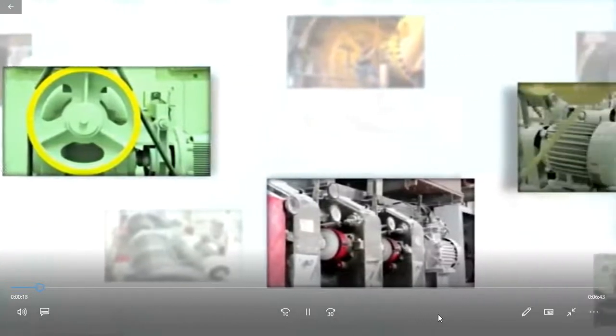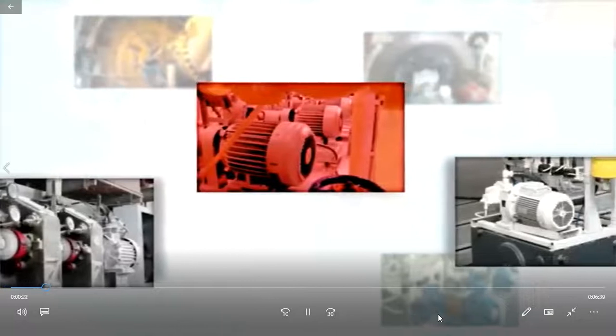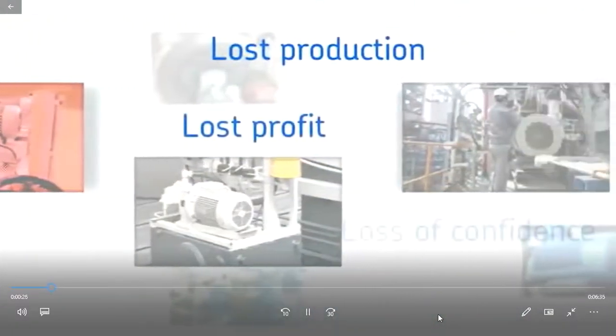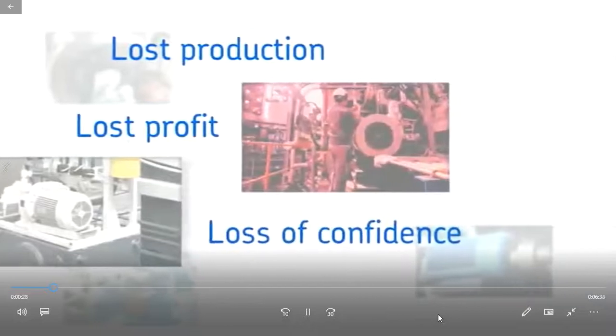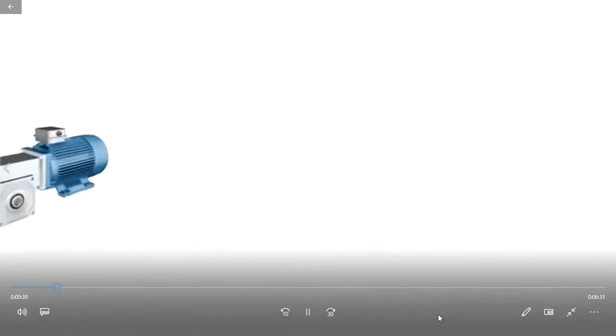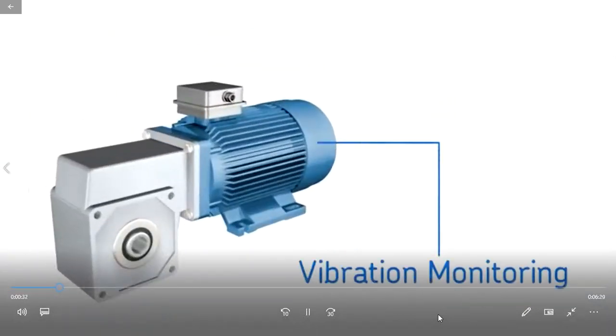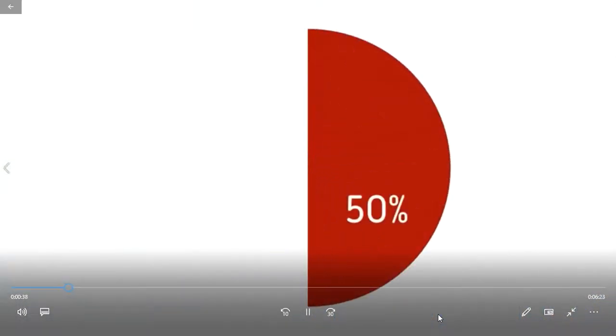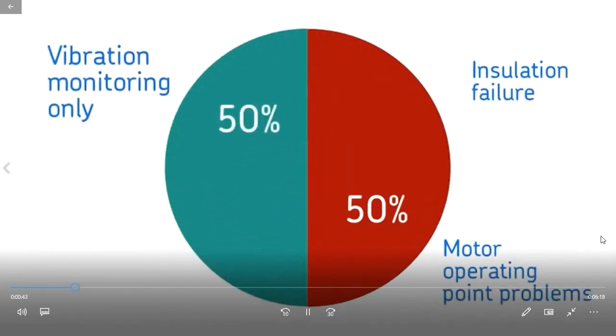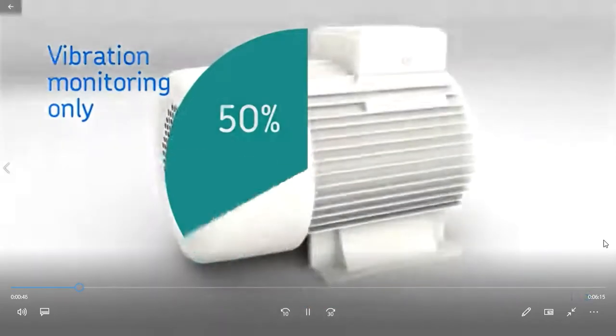Electric motors are the same. When these motors fail, the costs of downtime are very high: lost production, lost profit, and loss of confidence if the failures were unforeseen. Many sites use vibration monitoring on their motors. This is good, but vibration monitoring misses up to 50% of motor failures. These failures are due to insulation failure and motor operating point problems. Let's look at each.